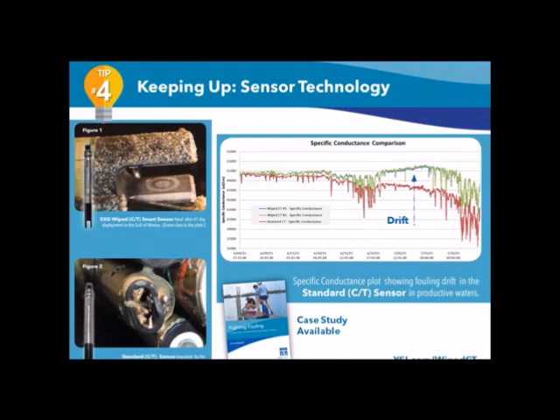So even within a few weeks into a deployment, a few days in some cases, your conductivity data could be off 10 or 15% if you're using an unprotected sensor. So, to reiterate, tip number 4 is always to keep up with new technology, because manufacturers are always coming up with something new that can help you keep sensor fouling at bay. And that may be, in this case, a wiped conductivity sensor, but certainly there are other advances that are happening all the time that could be helpful for you. So keep an eye out for that sort of stuff.